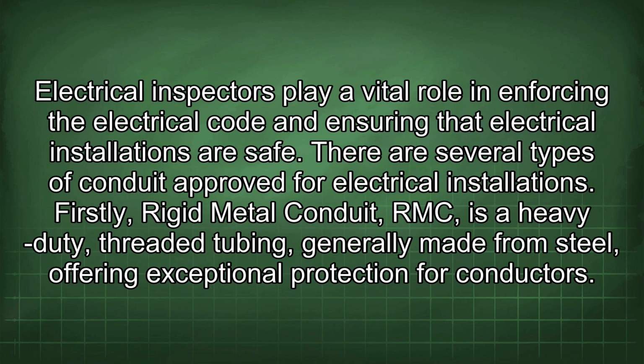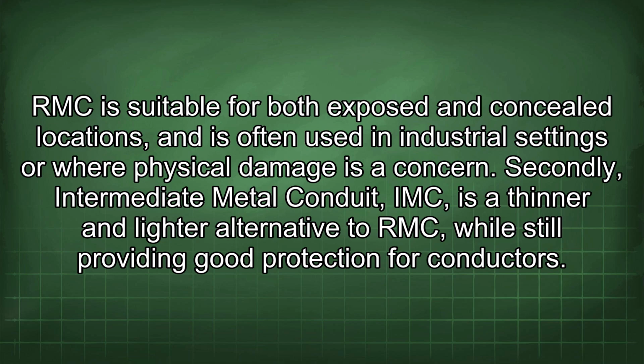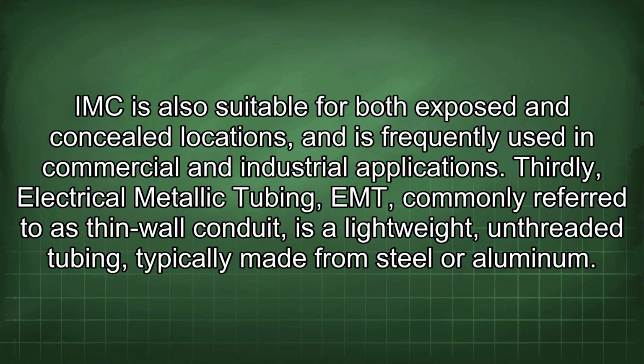Firstly, rigid metal conduit, RMC, is a heavy-duty, threaded tubing, generally made from steel, offering exceptional protection for conductors. RMC is suitable for both exposed and concealed locations, and is often used in industrial settings or where physical damage is a concern. Secondly, intermediate metal conduit, IMC, is a thinner and lighter alternative to RMC, while still providing good protection for conductors.